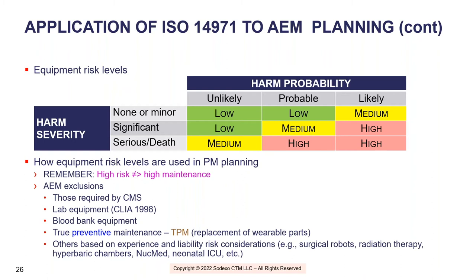Again, when planning for this, remember the CMS requirements, like lab equipment with CLIA, blood bank equipment. These require OEM frequency and task. TPM, or true preventive maintenance, you're actually replacing something, O2 cells, hoses, filters, whatever the case may be, true, that's going to actually be a PM. We don't do a lot of those today. Maybe anesthesia, maybe a 10,000 hour on a ventilator. So those you'll want to still kind of keep on an OEM basis.